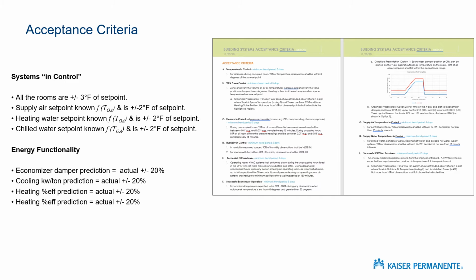So if you could just say those things, hey, all my zones are plus or minus 3, all my main system temperatures are plus or minus 2, you have achieved control. You have a building that's in control, right? Now, it may be a complete energy hog or a complete dog, but it will be in control. And that's when it's safe to move occupants in, by the way, is once the systems are in control.